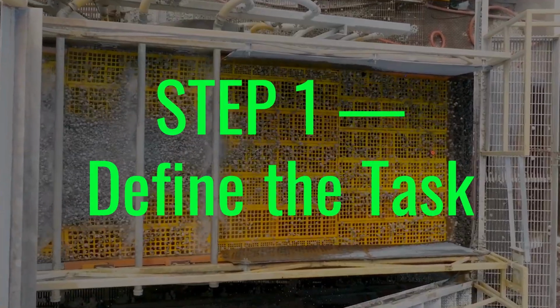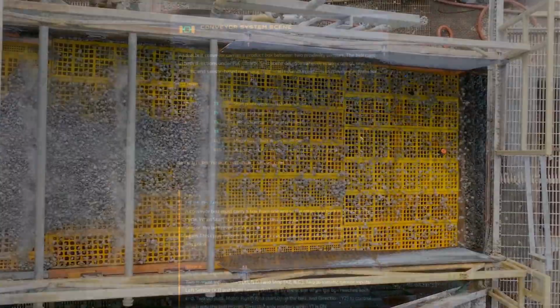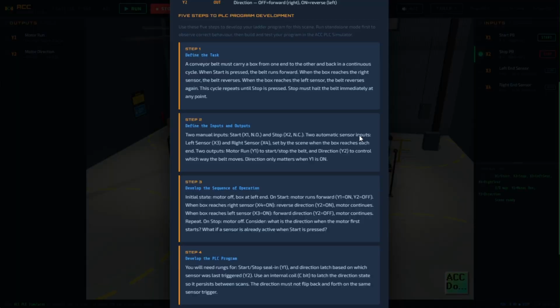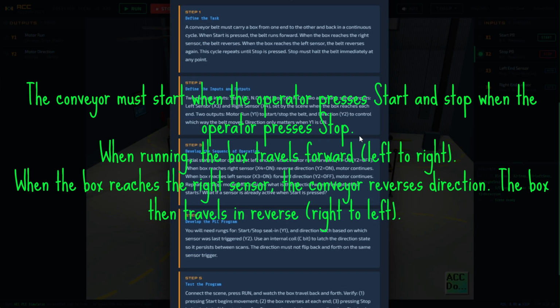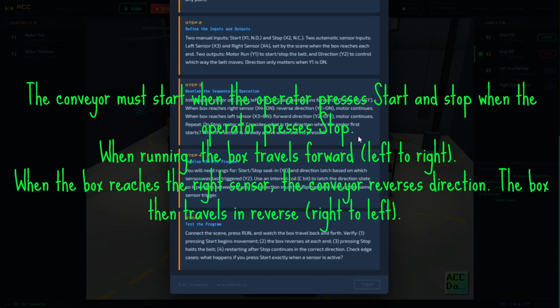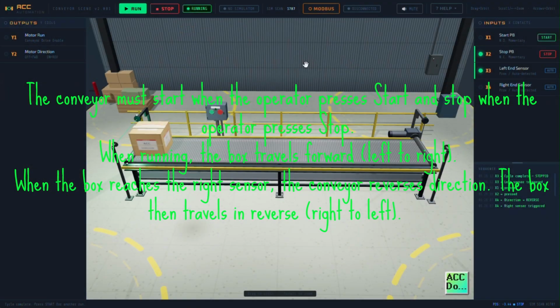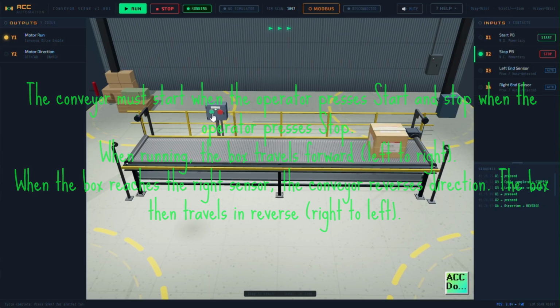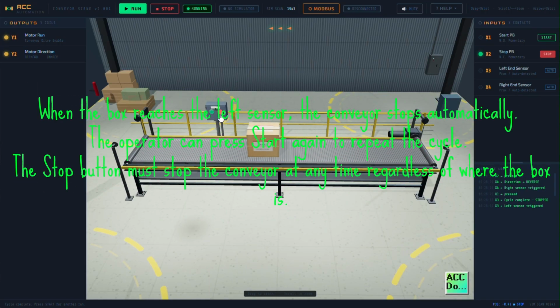Step 1. Define the task. Write down in plain English what the system must do before you touch any ladder logic. The conveyor must start when the operator presses start and stop when the operator presses stop. When running, the box travels forward from left to right. When the box reaches the right sensor, the conveyor automatically reverses direction. The box then travels in reverse from right to left. When the box reaches the left sensor, the conveyor stops automatically. The operator can press start again to repeat the cycle. The stop button must stop the conveyor at any time, regardless of where the box is.